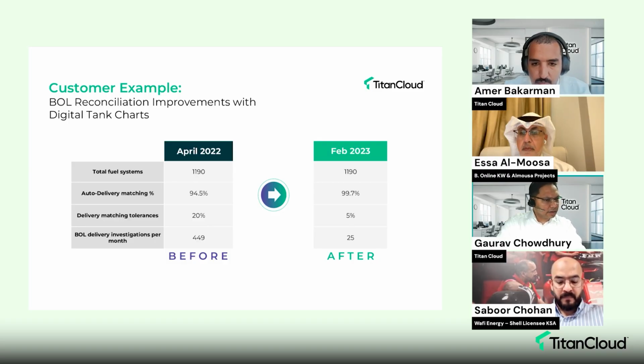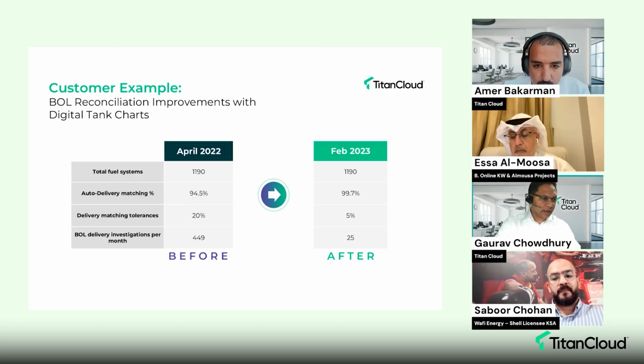In this example from a customer, with our tank gauge calibration and our algorithms, we were able to tighten the threshold. If you look at the lowest number, from 449 to 25, that is the amount of investigations that were needed. So we took the noise out of the system. We pushed for a tighter threshold, and we helped the customer with better investigations and results with BOL reconciliation. Tank gauge calibration is a critical part of that, because with any calibration you're looking at how much fuel is in the tank, and if you can improve that accuracy, it has a downstream effect as well.